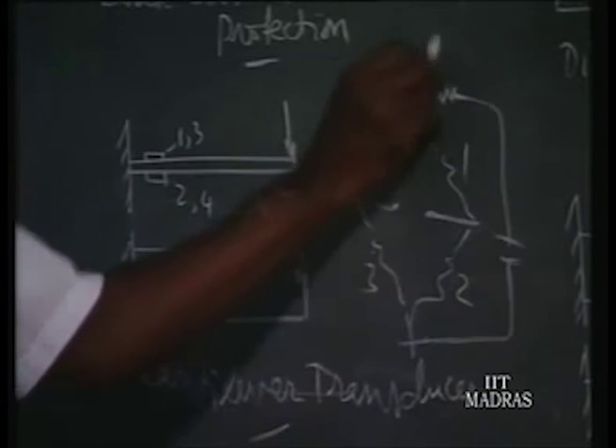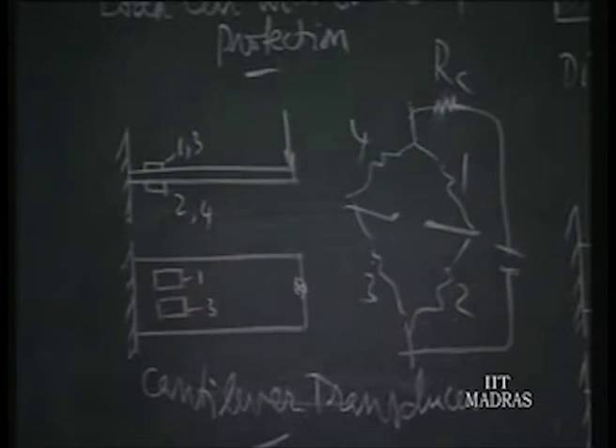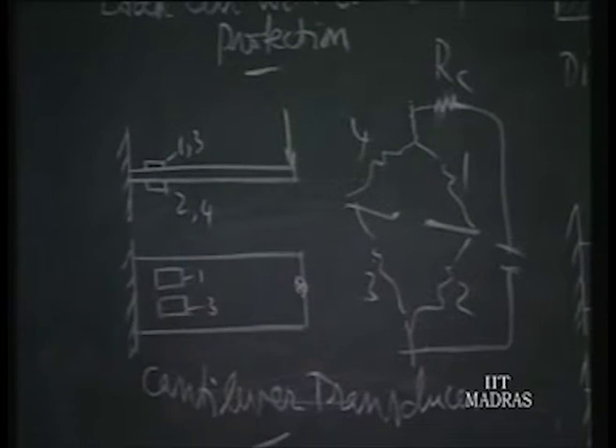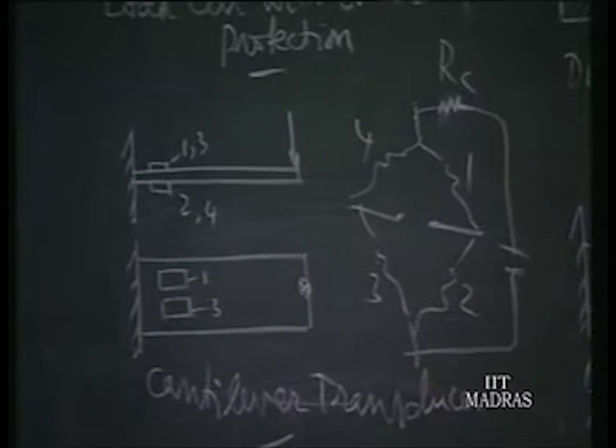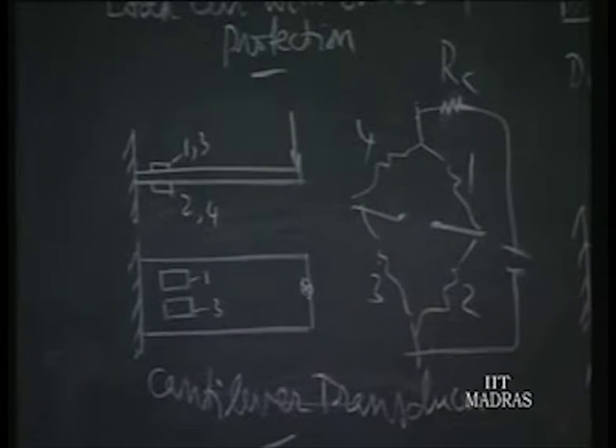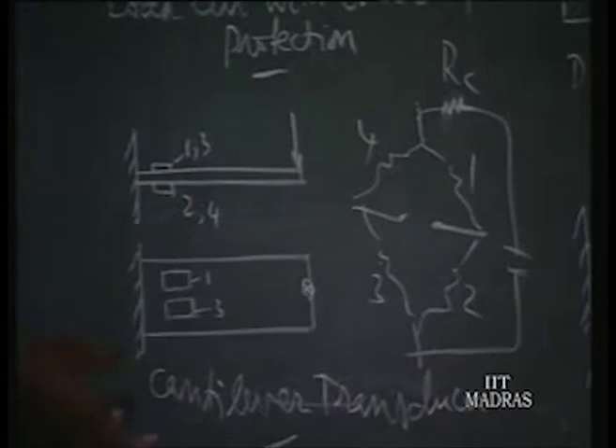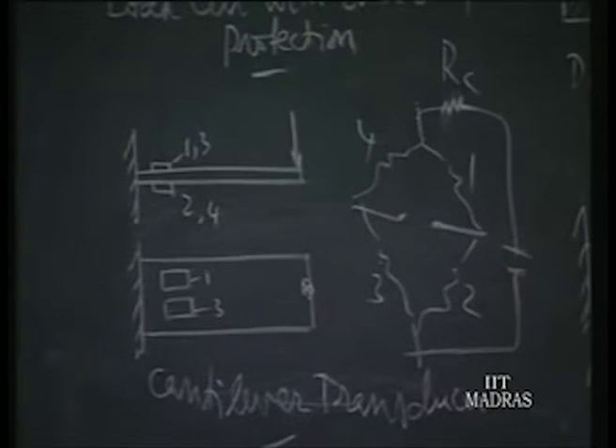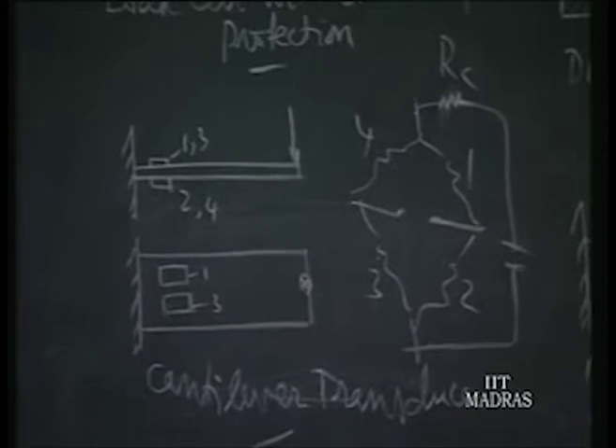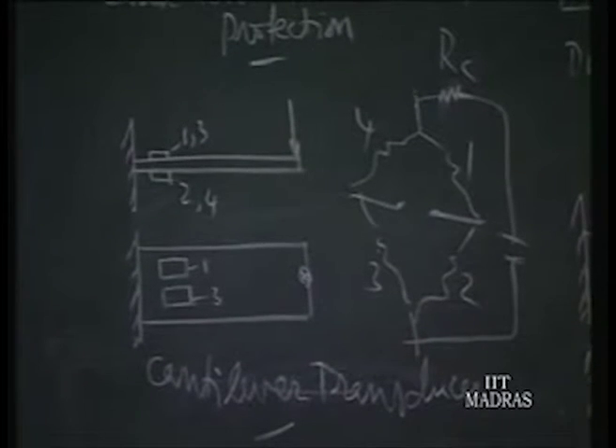And for accounting for the Young's modulus change due to temperature, we connect RC. The same circuit we can have. So this is for smaller load ranges, where we can go for this cantilever type. By having different thickness and different length, we can have different load ranges in this. It's a very versatile, useful principle.